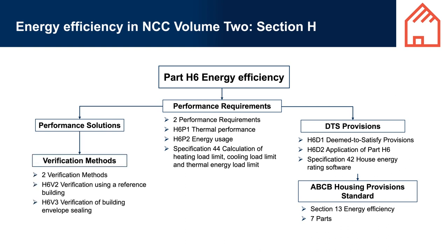Two verification methods exist. H6 V2 Verification Using a Reference Building can be used to comply with H6 P1. This method requires comparing the performance of the proposed building with a reference building that meets the DTS provisions. H6 V3 Verification of Building Envelope Sealing can be used to meet the building sealing part of H6 P1. It tests air leakiness using the blower door test, requiring the building envelope to achieve air permeability of not more than 10 cubic metres per hour per metre squared at 50 Pa pressure, tested in accordance with AS/NZS ISO 9972 Method 1.